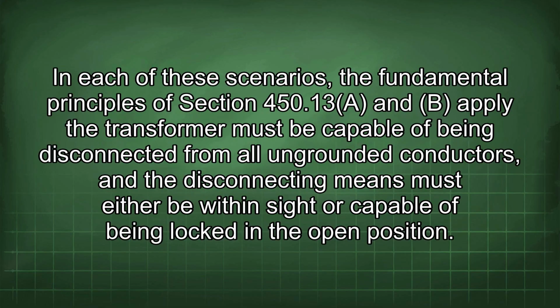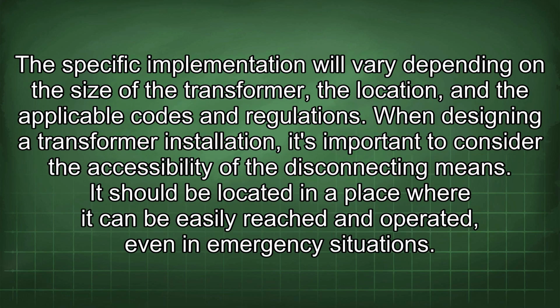In each of these scenarios, the fundamental principles of Section 450.13 apply. The transformer must be capable of being disconnected from all ungrounded conductors, and the disconnecting means must either be within sight or capable of being locked in the open position. The specific implementation will vary depending on the size of the transformer, the location, and the applicable codes and regulations.